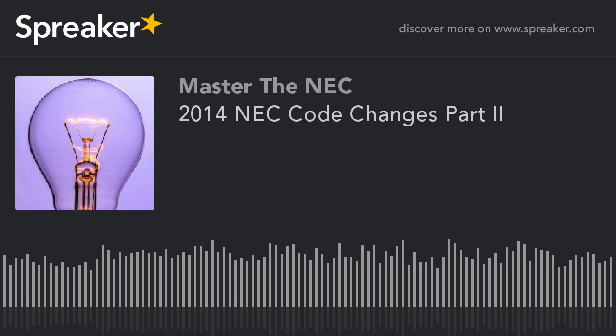So the next change we're going to look at, we're kind of staying in 210 here. We're going to look at 210.52(G), which deals with basements, garages, and accessory buildings. There were some changes here that we need to be aware of. It created a list format, so now you've got G1, G2, and G3, G1 being garages, G2 being accessory buildings, and G3 being basements.